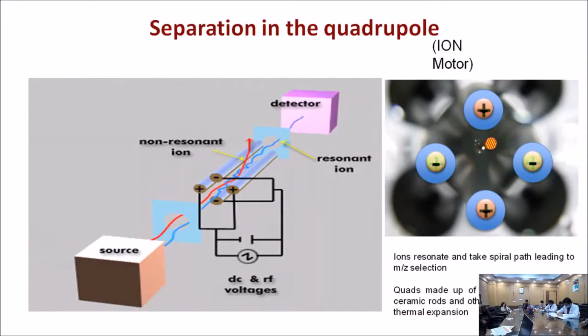You can separate a particular pseudomolecular ion because it resonates under a particular combination of these voltages. The lenses are arranged with different charges, guiding the ion in the positive direction towards the detector, forming a trajectory inside the quadrupole so it can reach the detector. So you're selecting a pseudomolecular ion using a particular combination of DC voltage and RF, and the resonant ion gets separated out.